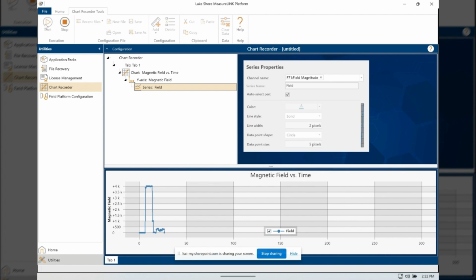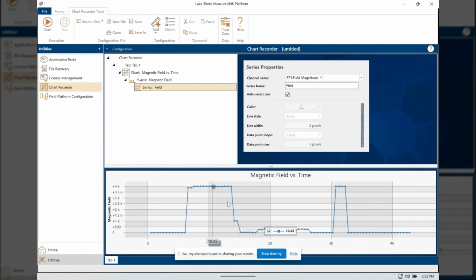The really helpful part about chart recorder is you don't have to be there doing any kind of data collection. You can physically manipulate where the probe is located as you are troubleshooting, or perhaps looking at your design to try to find exactly where the sweet spot is as far as the magnetic field strength. Once you're done collecting data, you can manipulate the data as well. It doesn't have to be at the end. And you can export that data to a CSV. You can also export the chart as a bitmap image. So lots and lots of tools available for you for that fast data collection.